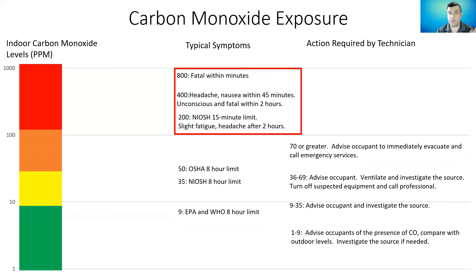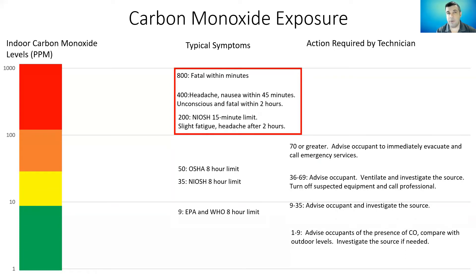Above 70, that's where it gets really dangerous. At 200, NIOSH says a 15-minute limit, and then it starts to seriously affect your health — you'll start noticing slight fatigue and headache. After two hours, it gets even worse. At 400, you're going to have a headache and nausea within 45 minutes, and you could be unconscious or even die if exposed for close to two hours. At 800 parts per million, that is very high concentration — you could be dead in a couple of minutes.